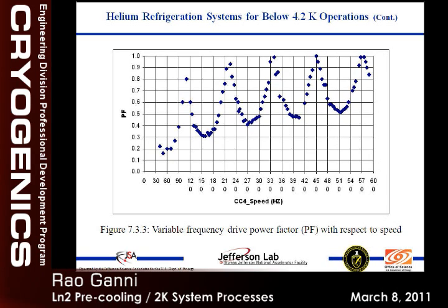So now that we know the root cause, let's find out the pump down path, like I was telling you before, so that no more than one compressor will be at the minimum power factor when we adjust the relative speed ratios. So we worked out the algorithms between all the four so that no one reaches the minimum at any given time, and we had a successful pump down. So finding out the cause of the problem itself sometimes is very difficult.